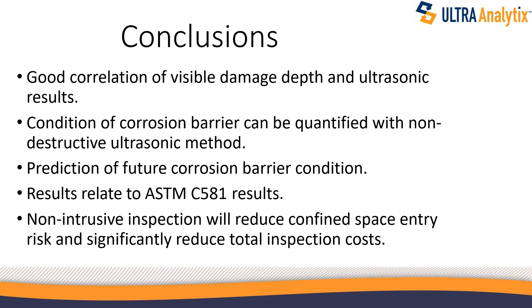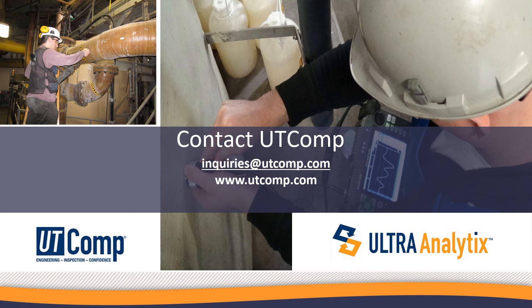The conclusions we offer are that we get good correlation of visible damage depth and ultra-analytics results. The condition of the corrosion barrier can actually be quantified with non-destructive work. We can predict future corrosion barrier condition, and the results actually relate back to the same tests that were used to help determine what materials you should have built it from. This non-intrusive inspection will reduce confined space entry risk and significantly reduce total inspection costs. Thank you very much for listening. I invite you to contact UT Comp if you'd like any more information — inquiries@utcomp.com or visit our website. It's been my pleasure. I'm Jeff Clarkson. Thank you.